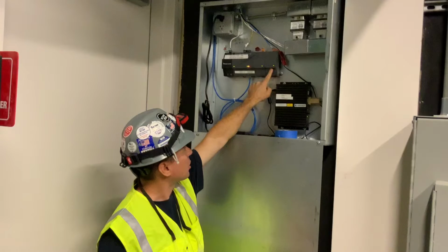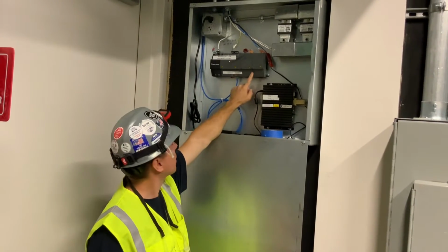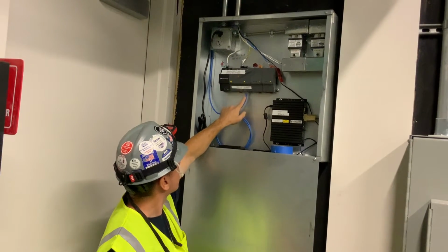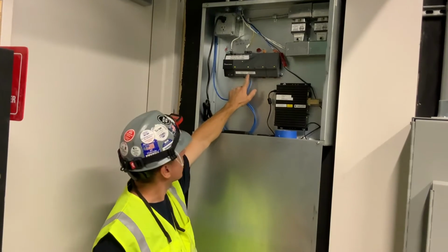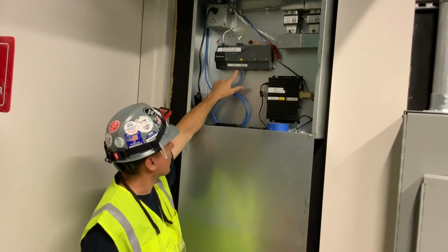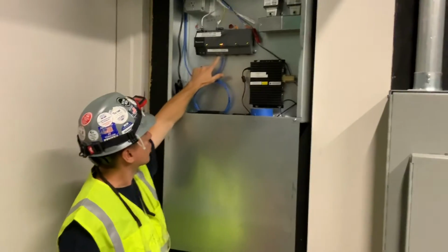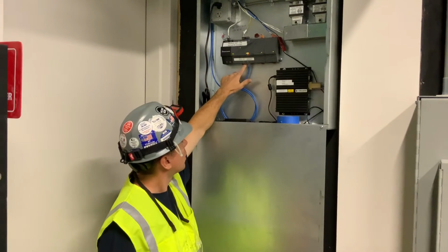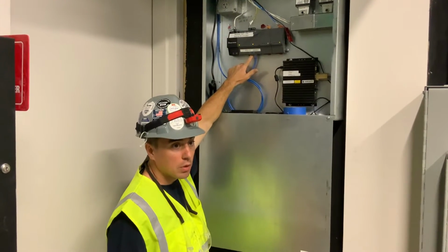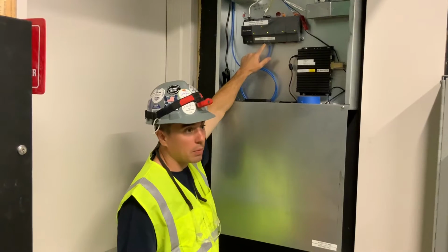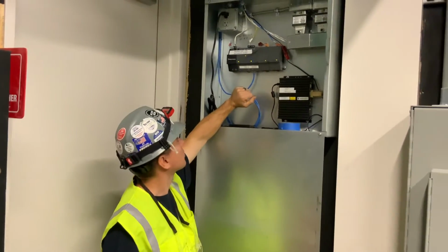If they still have comm, they should be blinking like this. That's spelled out on there. It also has primary port, which is labeled with the IP address, and then the service port. So if this cable were to get moved over to the wrong port, it could be plugged in and you would have lights, but it wouldn't be communicating with the graphics.